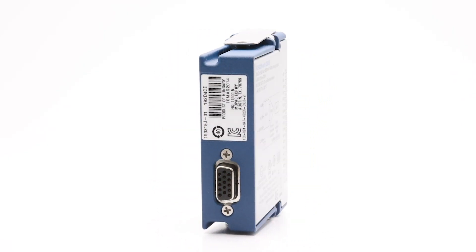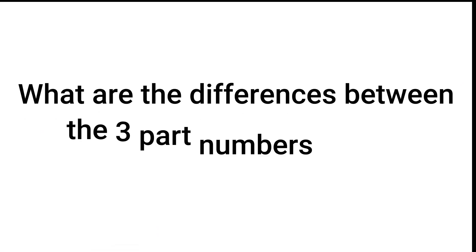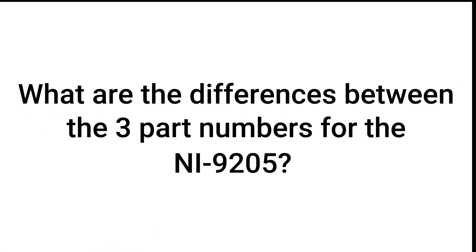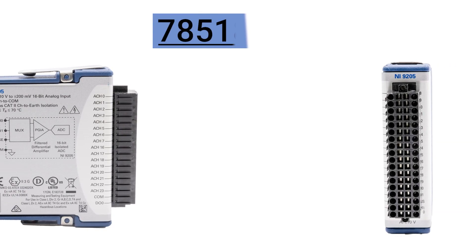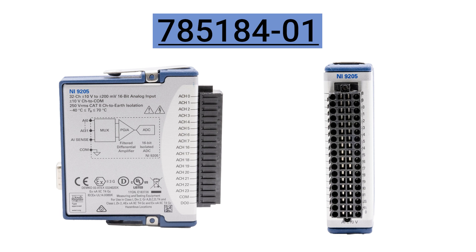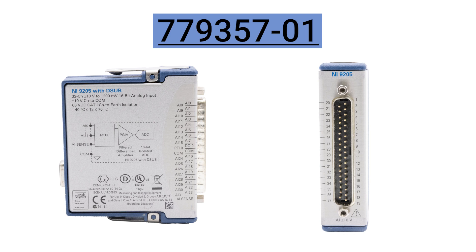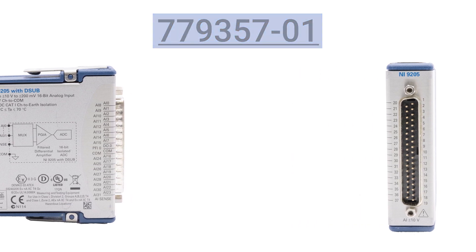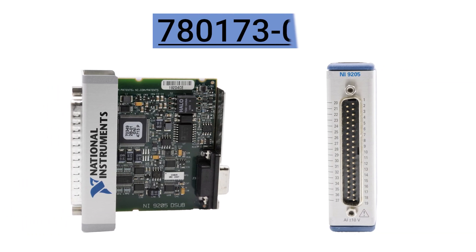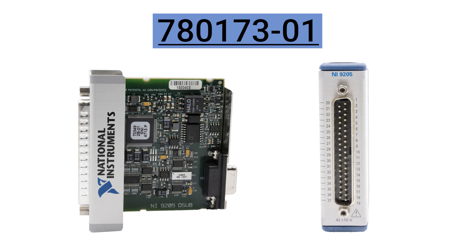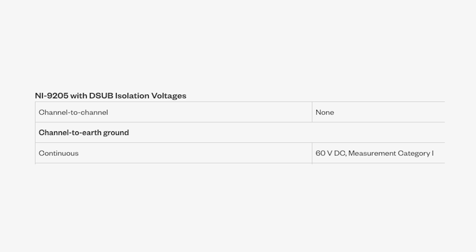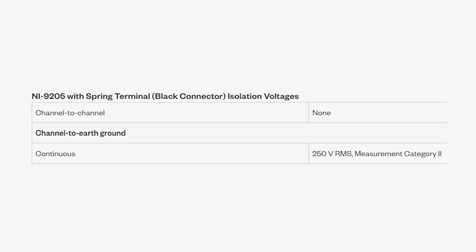Here are some common questions about the NI9205. What are the differences between the three part numbers? The NI9205 module has several connector types available. Part number 785184-01 has spring terminals and is not conformal coated. Part number 779357-01 has D-sub front connectors and is not conformal coated. Part number 780173-01 has D-sub front connectors and is the only conformal coated version. D-sub variants have 60VDC channel-to-earth ground isolation, while the spring terminal variant has 250V RMS channel-to-earth ground isolation.